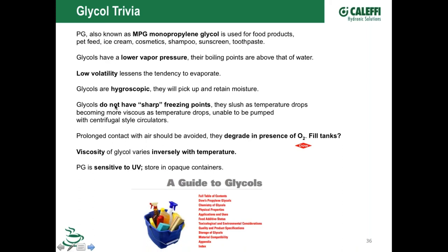Here's something interesting about glycol: it doesn't have a sharp freeze point like water, which freezes at 32 degrees. Glycols will first turn into a slush as you approach their freeze point, and that slush gets thicker and thicker until it reaches a freeze-burst point. So you've got a little wiggle room on those numbers - there's a point where you can no longer pump it, but it won't burst your pipes and cause a problem.